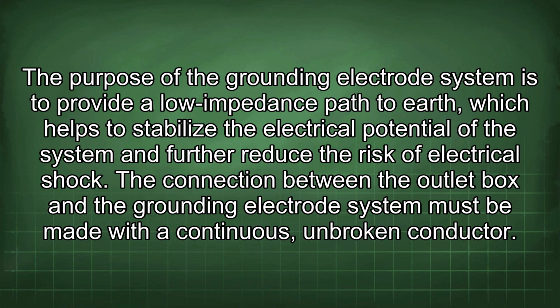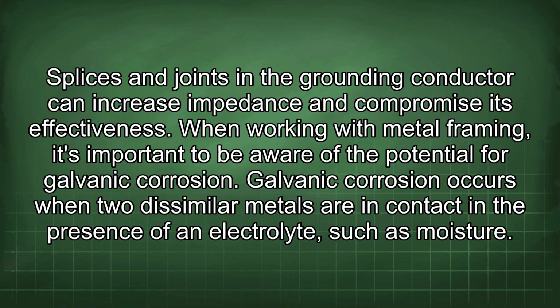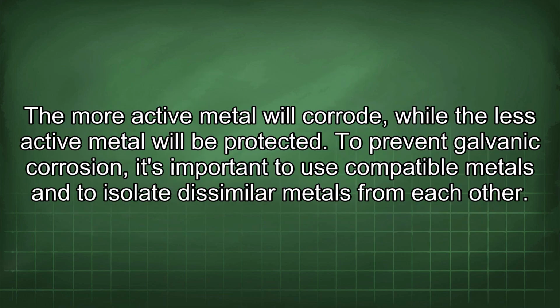The connection between the outlet box and the grounding electrode system must be made with a continuous unbroken conductor. Splices and joints in the grounding conductor can increase impedance and compromise its effectiveness. When working with metal framing, it's important to be aware of the potential for galvanic corrosion. Galvanic corrosion occurs when two dissimilar metals are in contact in the presence of an electrolyte, such as moisture. The more active metal will corrode, while the less active metal will be protected. To prevent galvanic corrosion, it's important to use compatible metals and to isolate dissimilar metals from each other.